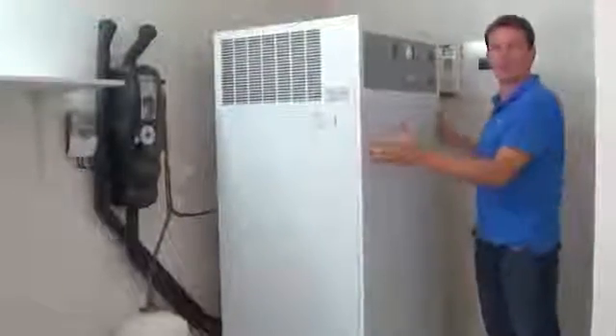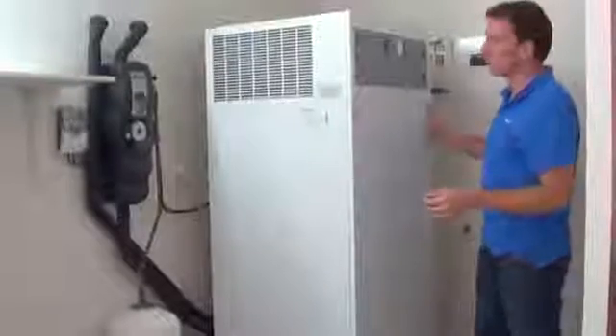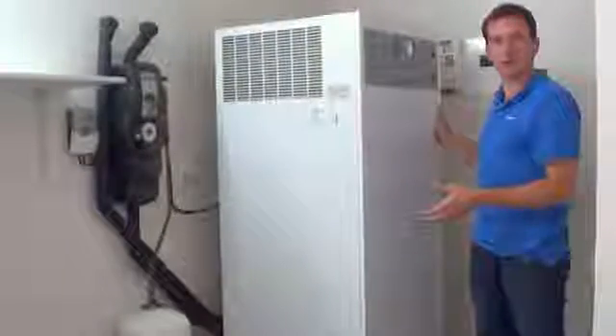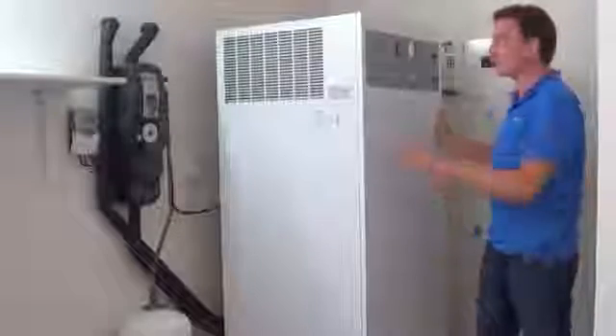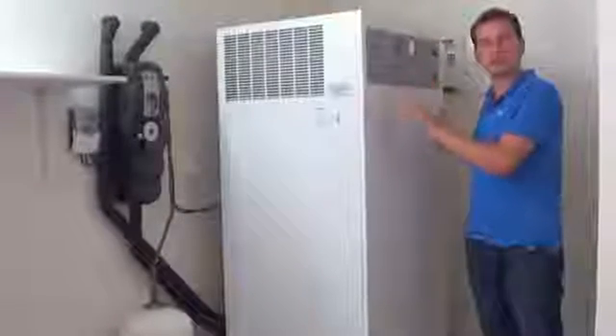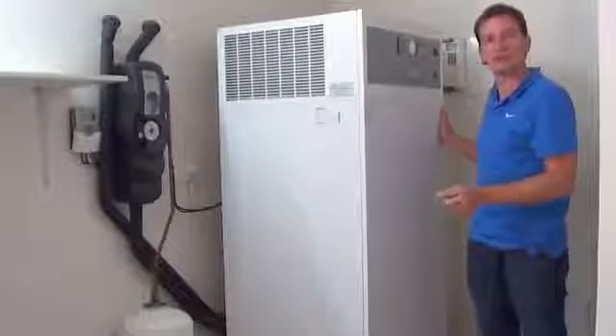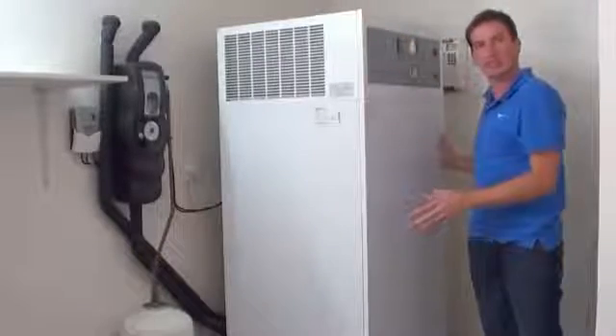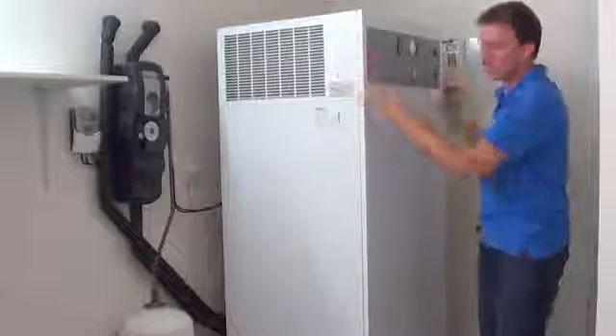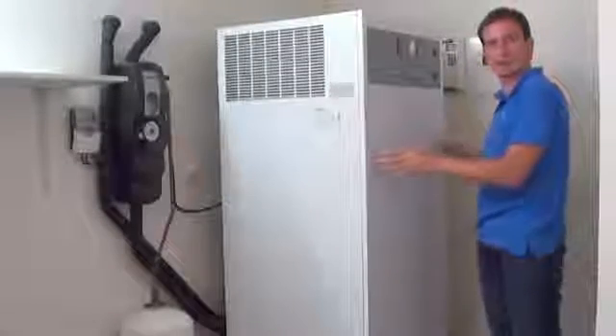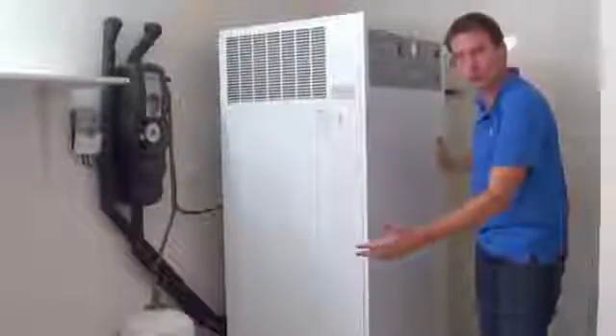This is as close as you're going to get to a pure refrigeration heat pump system. When people talk about a 75% heat pump saving, this is for an ideal refrigeration system. The 75% is a theoretical saving when you've got an integral heat pump. The minute I take my heat pump and I split it and I put the tank separately like this, your efficiency drops because of the circulation of the water to the heat pump and back.